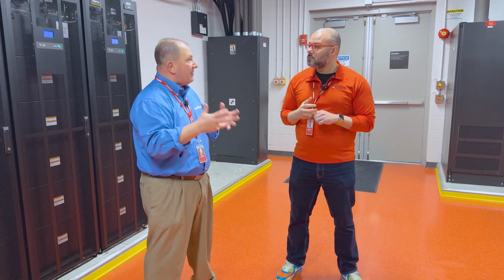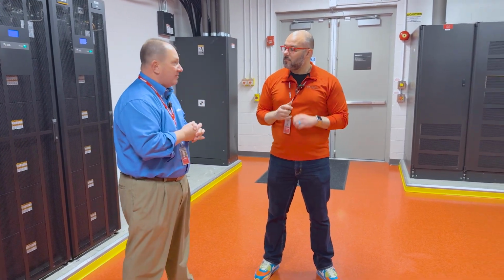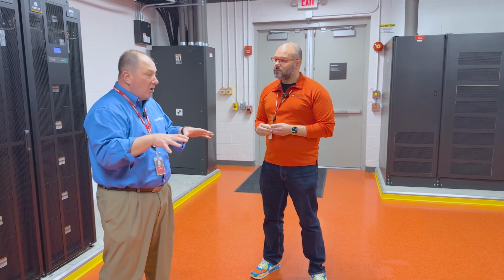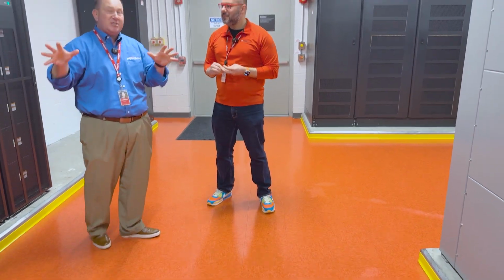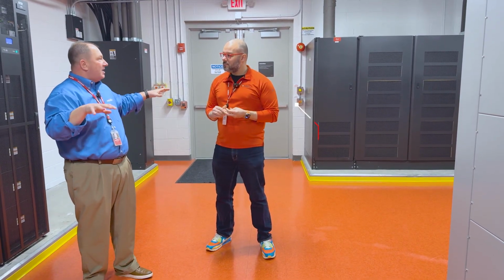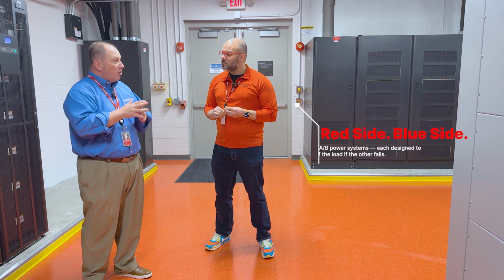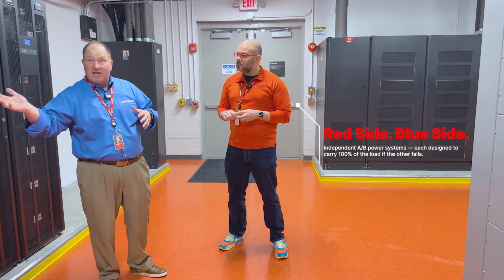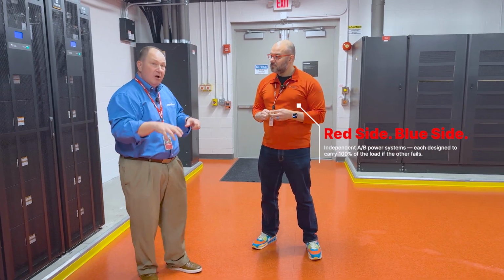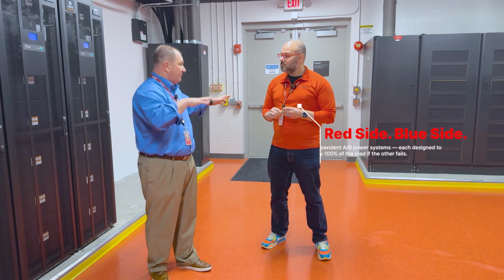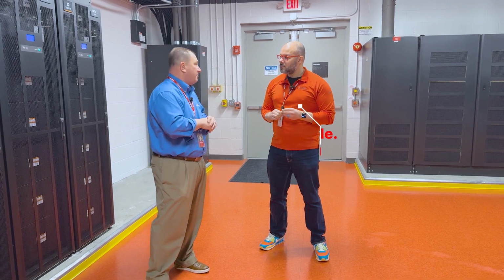We carry that theme all the way through our power plant to ensure that redundancy. We're built to 2N on the power plant redundancy - you can't build just one, you have to build two to provide that. These systems are designed to run at 50% load in normal operating scenarios. If one side fails, this entire room could fail, and that room can handle the load, and vice versa. So all this equipment is running at 50% load.